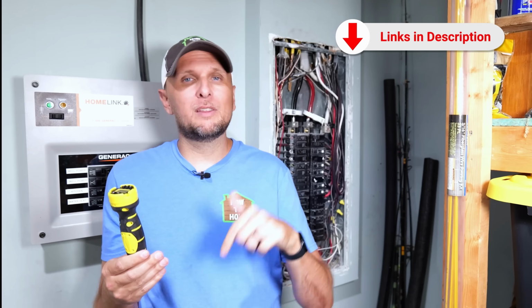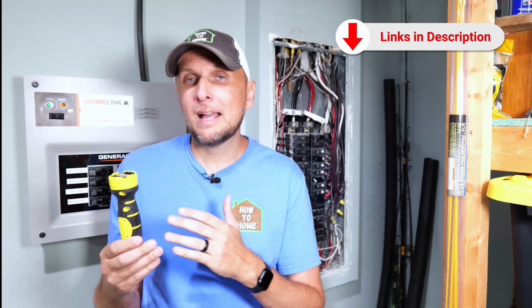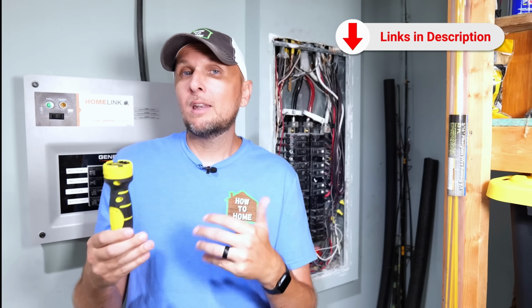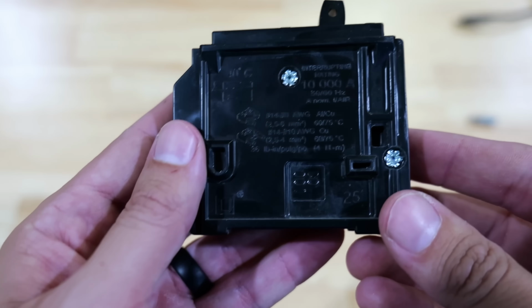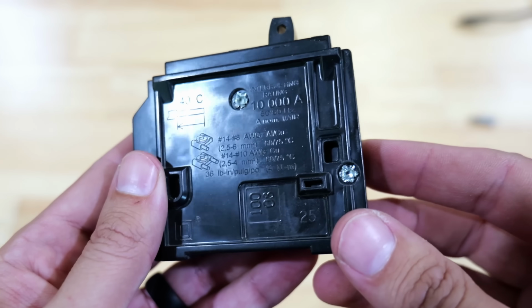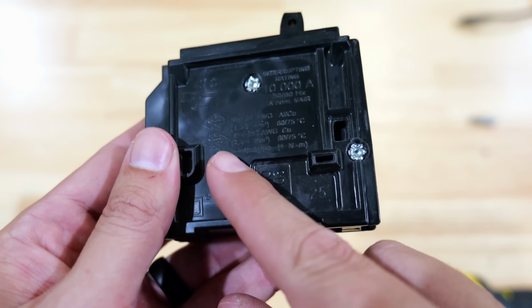I'll have links for everything down below, but once you have one of these, you can make sure you're getting everything torqued down to the proper specs. To find out what that is, check the breaker itself or the panel label, and you can usually find those torque specs there.